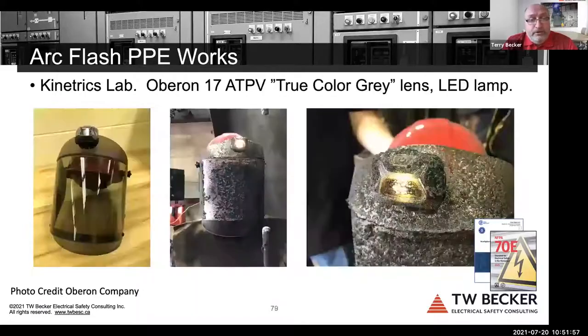So this is an Oberon arc-rated face shield. It's a 17 ATPV. I happened to get invited to Kinectrics when Jack Hirschman, who's the owner and the inventor of the Oberon products, was doing some testing on the 140 arc flash suit hood. And I said, Jack, can we arc flash my shield with the LED on? He said, go get it. I did. We arc flash at about 20, and you can see the LED still working. I was impressed. And that's just a Petzl LED on there. And that's what will happen to the shield. You'll see that sort of carbonization, and then the polycarbonate plastic is melted.